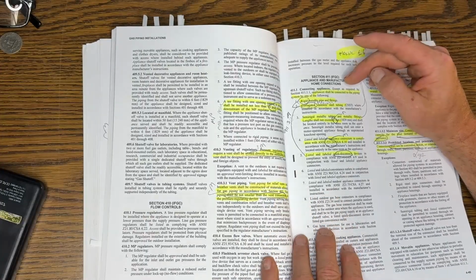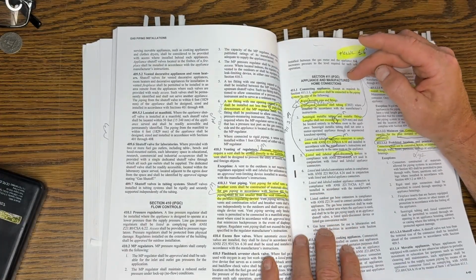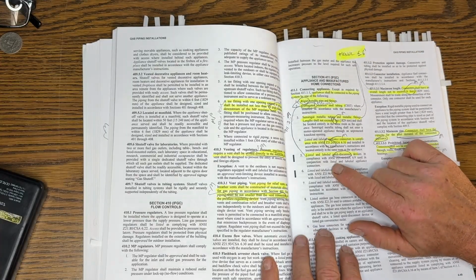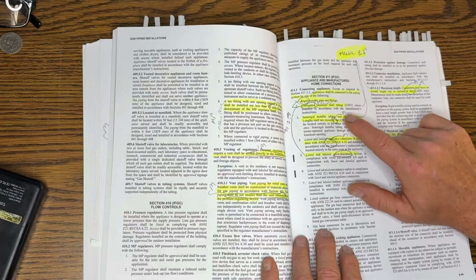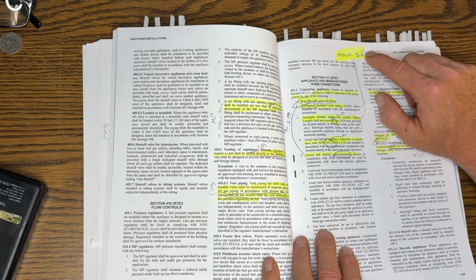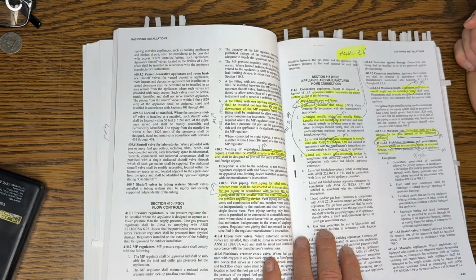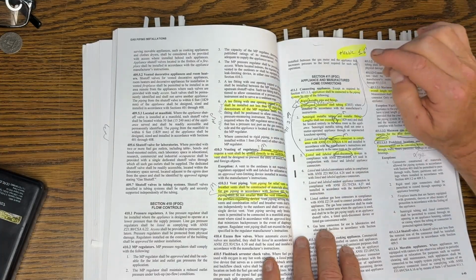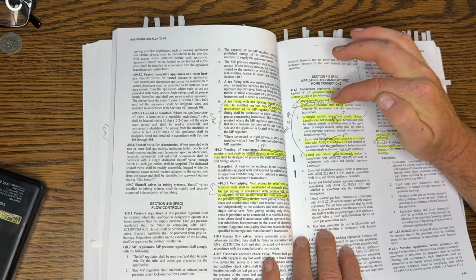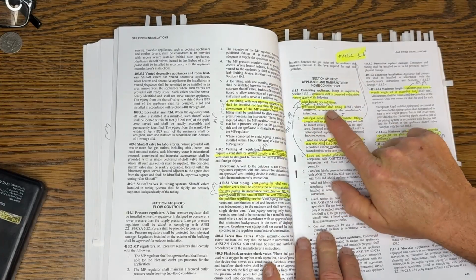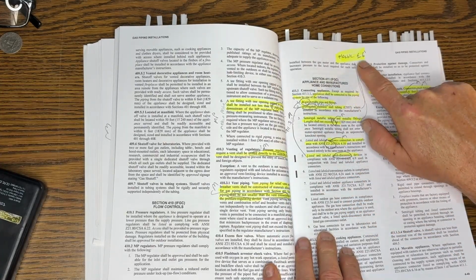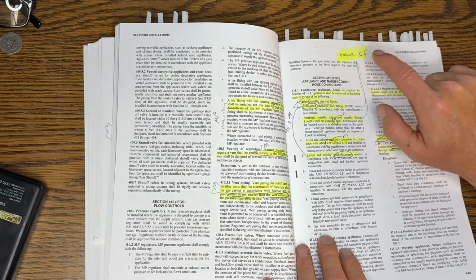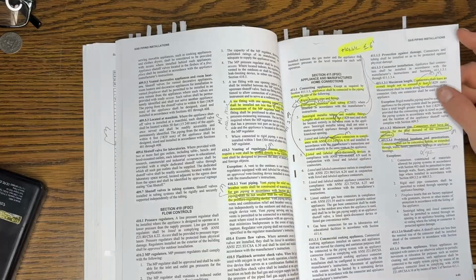Appliance and manufactured home connections. Let's see, there's a bunch of stuff here. So we had multiple questions here. The flexible lines are always less than 6 feet across the board. You have 6 feet there, 6 feet here, a very common thing, okay? Where installed in accordance with the manufacturer's instructions. Even here, corrugated stainless steel tubing, less than 6 feet. I highlighted this because it's an important answer. They asked this multiple times. Less than 6 feet is for a flexible tube, gas line.